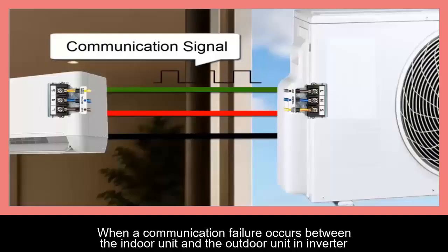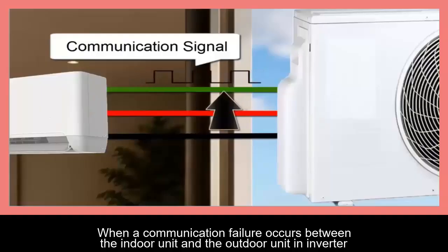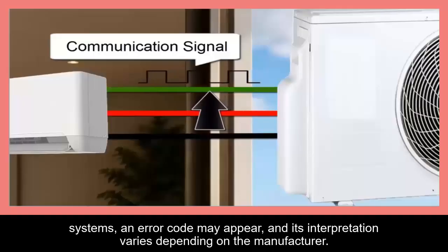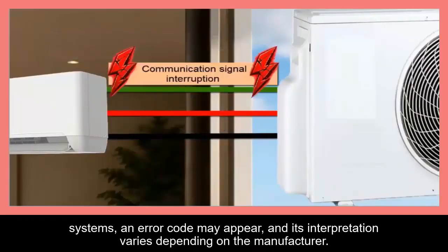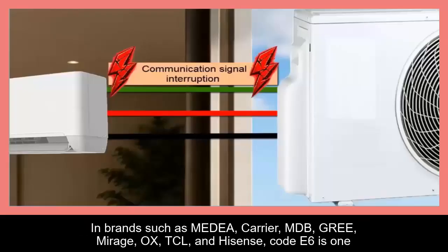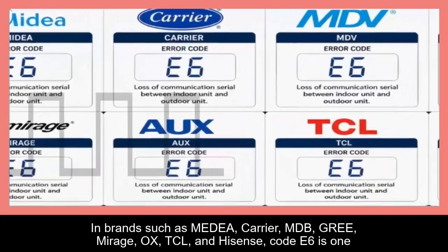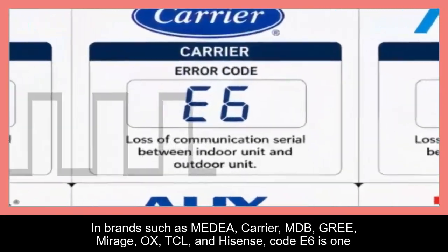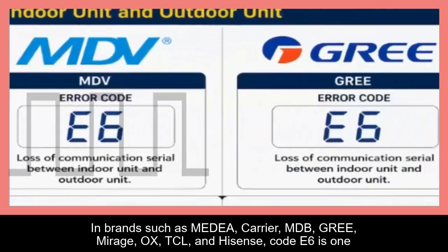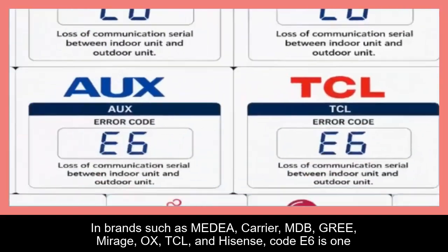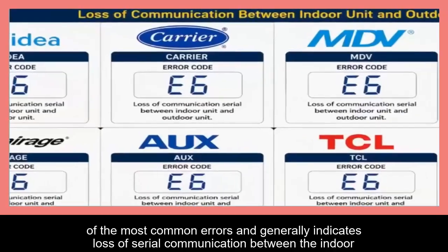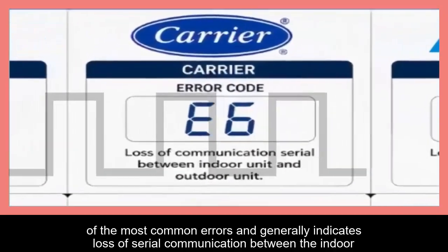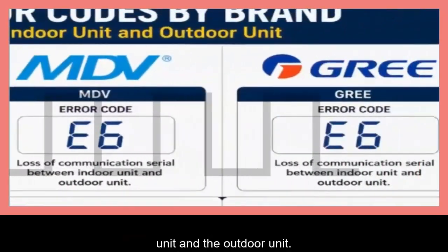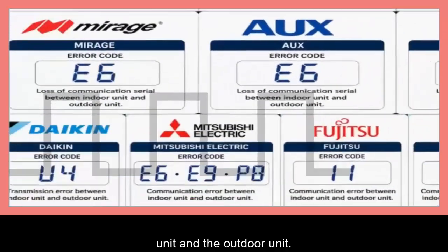When a communication failure occurs between the indoor unit and the outdoor unit in inverter systems, an error code may appear, and its interpretation varies depending on the manufacturer. In brands such as Midea, Carrier, MDV, Gree, Mirage, AUX, TCL, and Hisense, code E6 is one of the most common errors and generally indicates loss of serial communication between the indoor unit and the outdoor unit.